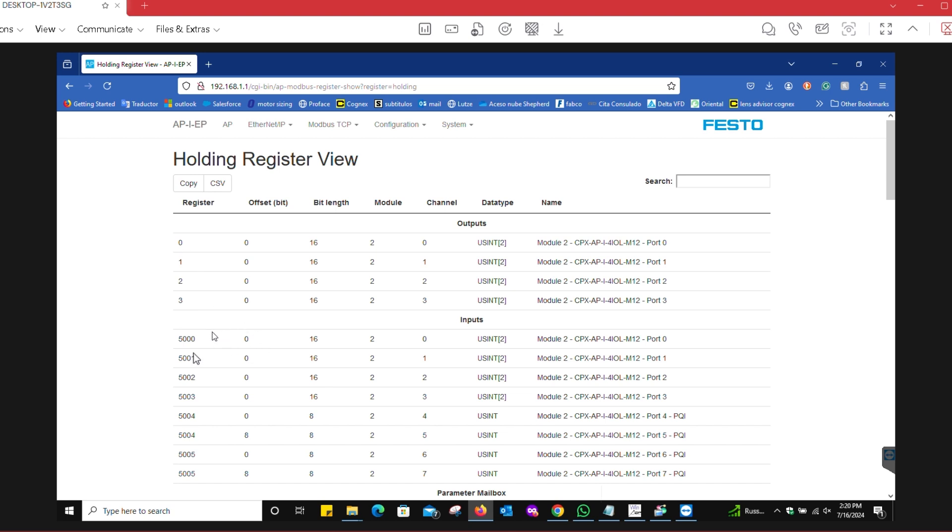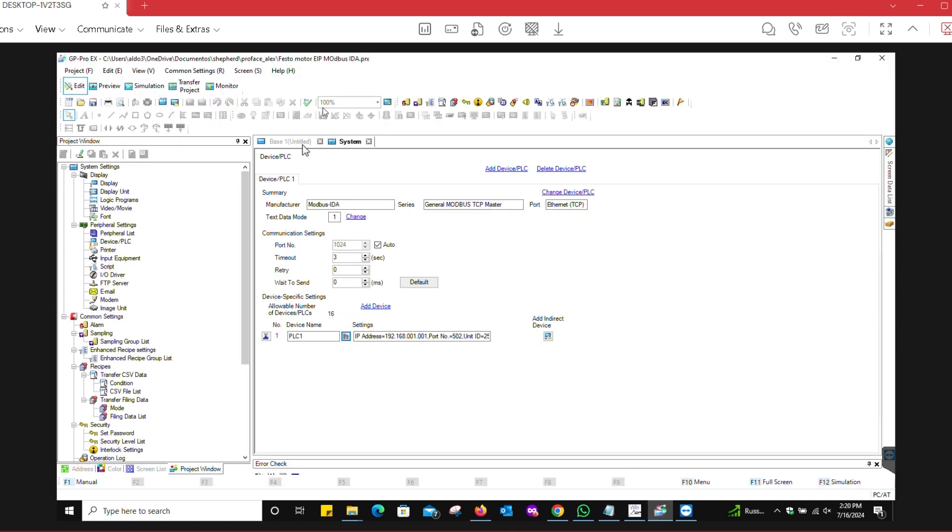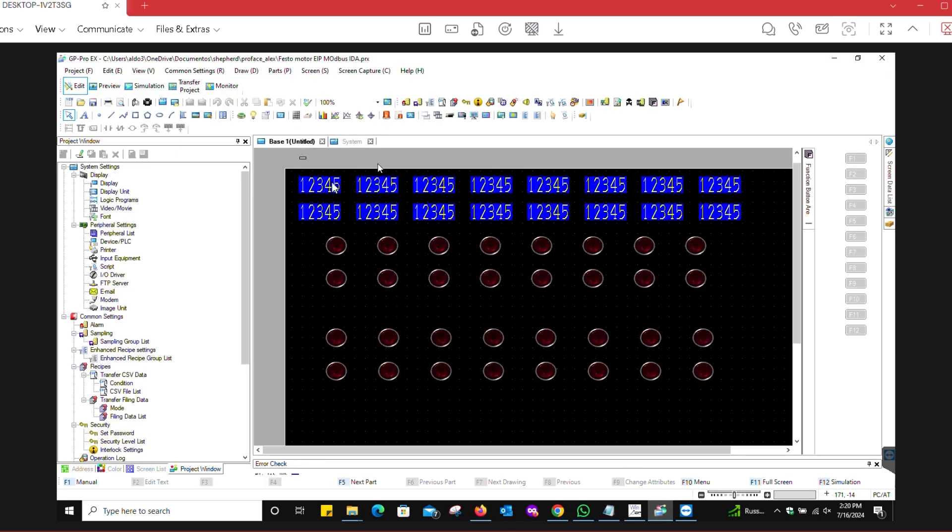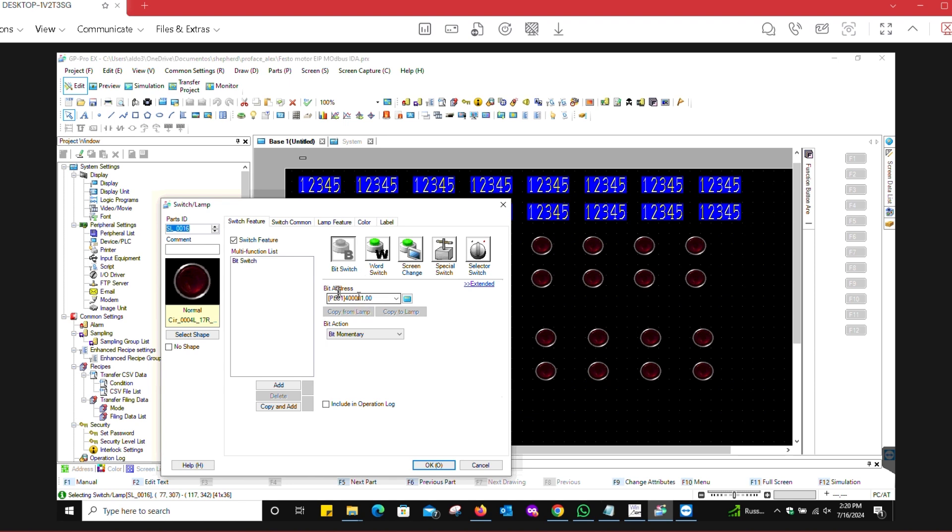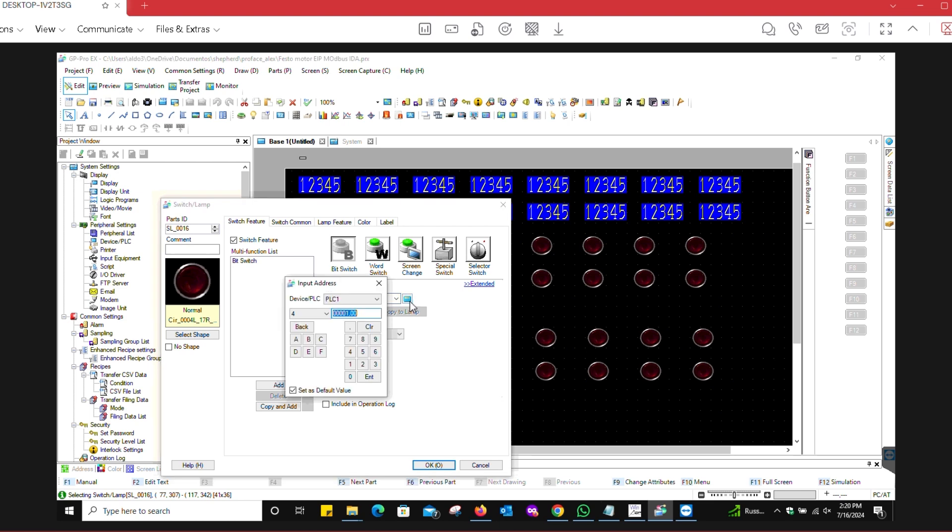If we go back to the configuration where we're creating our screen, this is going to be our first word for inputs and this is our first word for outputs. On the addressing, you're going to have to select 400,001 - remember the 400,000 that I mentioned, and there's an offset of one, so you say 400,001 point zero zero. That's for the first bit of that word.